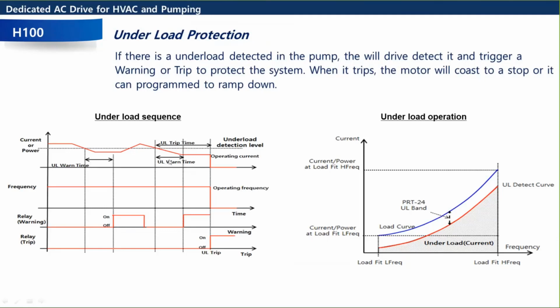So whatever time you go past is going to trigger something to happen, whether it's a warning or a trip, and it'll stop operations. So this can be used for belt breaks, right? Let's say you're running a fan and then the belt falls off or snaps. The fan won't be running, but the motor will be running indefinitely, and nobody will know until it gets hot and somebody complains, or until maybe a maintenance guy notices very low amperage on the keypad.